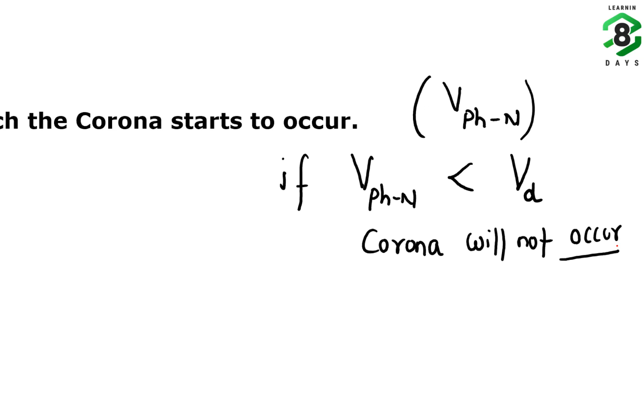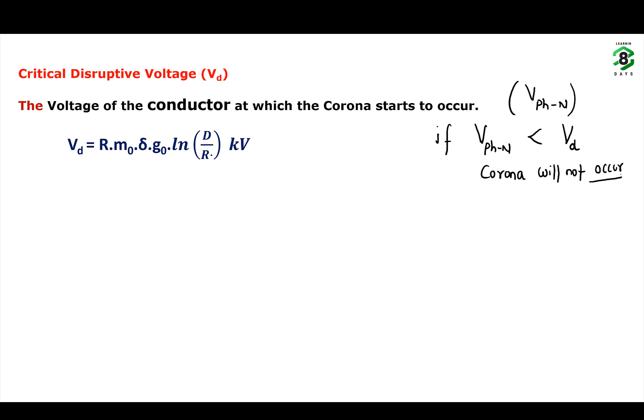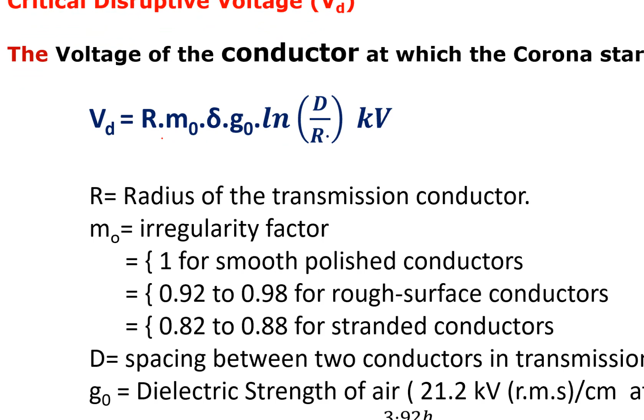So the minimum voltage at which corona starts to occur is called critical disruptive voltage. It is given by the product of the radius of conductor, m0, the irregularity factor, delta, the air density factor, and G0, the dielectric strength of air at normal temperature and pressure conditions, and again capital D is the spacing between the two conductors of the transmission line, and R is the radius of the conductor. So again I am telling you, critical disruptive voltage is the voltage between the phase and neutral or ground.